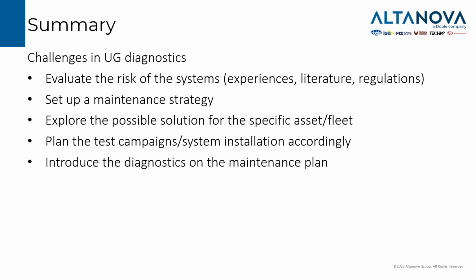At this stage, we can then set up a maintenance strategy. So we will decide which risk we can accept, which strategy we can put in place to reach that target, by exploring then the possible solutions for the specific cable line or for the whole fleet. Then we can plan testing sessions or system installations accordingly to the previous evaluation: the risk, the strategy, and the solution. And in the end, we will also need to build an action plan based on the possible output from the underground cables diagnostics, in order to enhance the efficiency of the diagnostic techniques put in place.